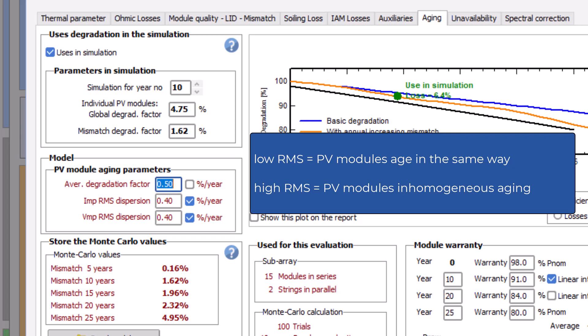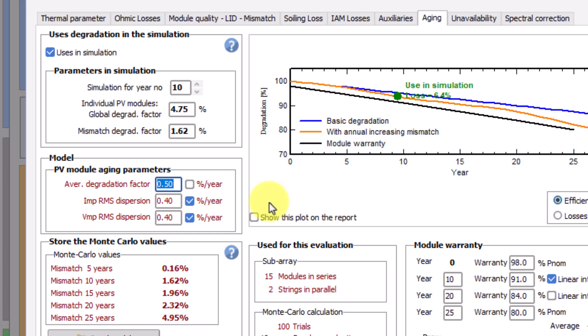A large value would correspond to a more inhomogeneous aging of the PV modules. Here we shall define an RMS dispersion of 0.6% per year for the current and 0.5% per year for the voltage. When you modify the RMS dispersion, you observe that the mismatch degradation factor in parameters in simulation changes as well.